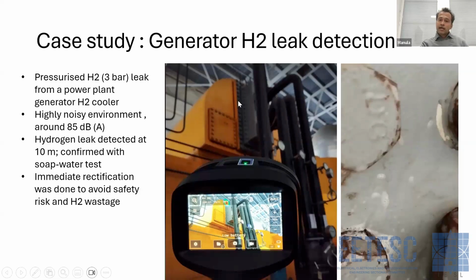But as I explained earlier, this kind of small hydrogen leak would generate ultrasound that would have dominance over this background noise in the high frequency ranges. So in this case, the camera has been able to effectively locate this leak point from one of the bolts. They have been using soap water to validate this leak. When they spray soap water on this bolt, it would form these air bubbles, or hydrogen bubbles in this case, so they can validate this leak. In this case, the leak is being inspected from about 10 meters away. So it provides a safe distance to inspect this kind of explosive gas leak, and it is also very quick and efficient.